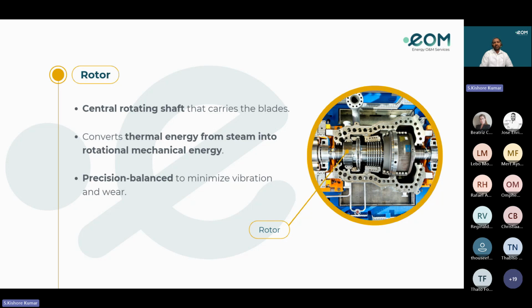The function of the rotor is to convert steam energy into rotational motion, transfer torque to the generator, and also support turbine blades. As for the material, in a solid forged rotor, the entire rotor is made from a single forged piece of steel. The rotor is usually made from high alloy steels, for example chrome, molybdenum, nickel alloys, in order to resist centrifugal forces, thermal stresses, corrosion, and erosion from the wet steam. So the rotor is literally the heart of the steam turbine. Everything revolves around it, and any damage or imbalance can lead to major outages. So it is recommended to do high speed balancing during the major outages.